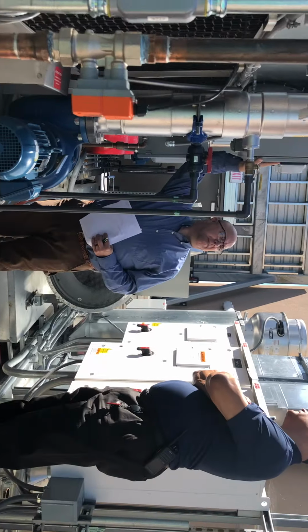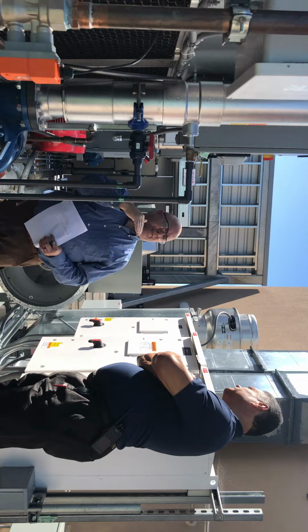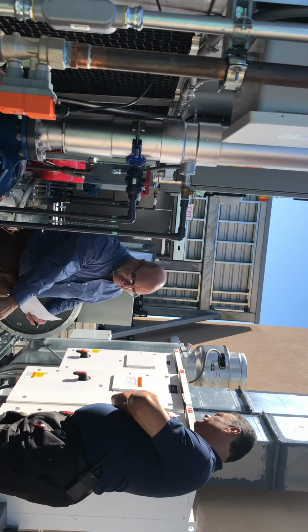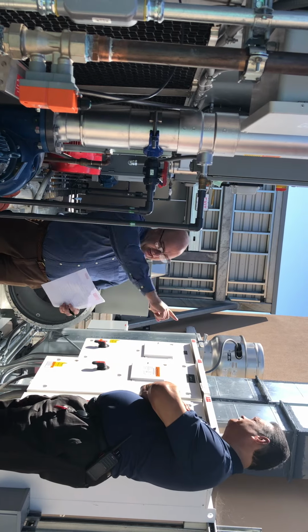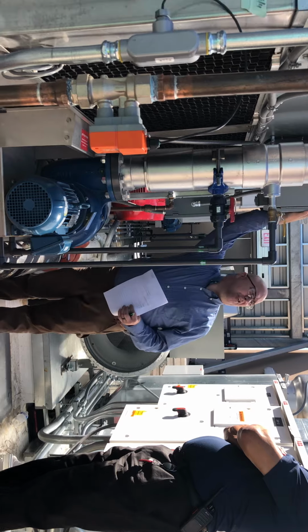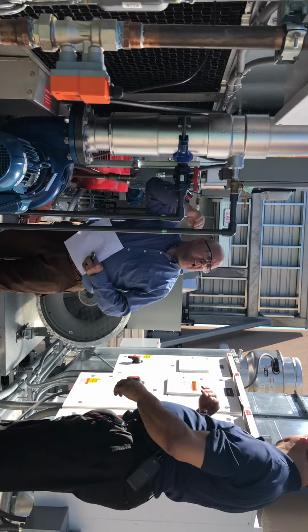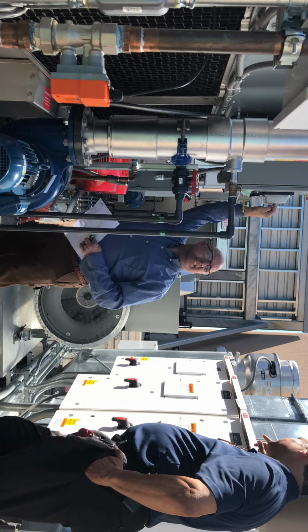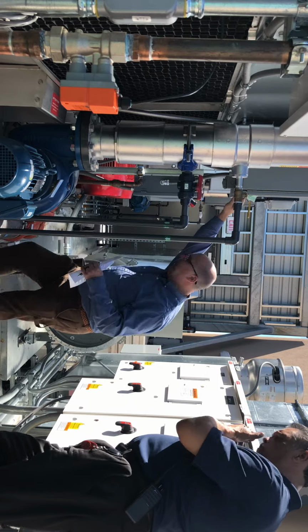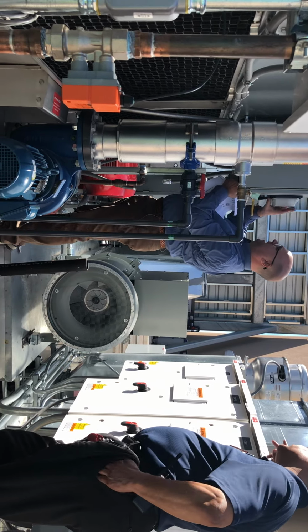The cooling towers themselves, I actually don't do a whole lot of control on. I simply say if the water coming back from the building, and that's actually the pipes you're standing on right there, if that water is too hot, if it exceeds 80, I turn on the cooling towers. Now there's two sets of cooling towers, but they run by their own set point here. Okay. Do we know what the set point is on? I believe right now it's dialed into 85, but we'll take a look.